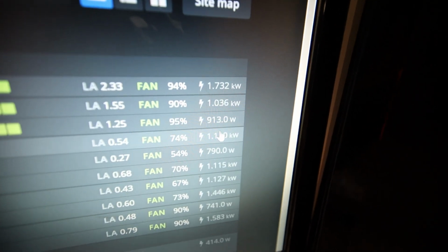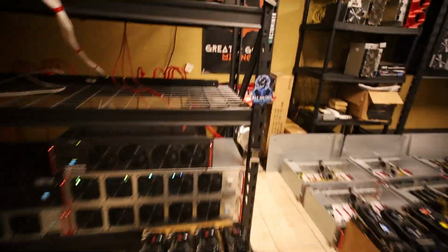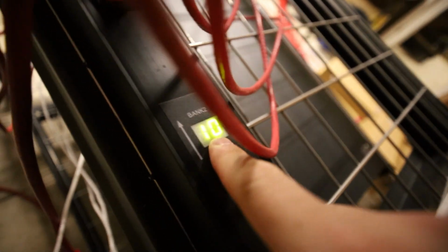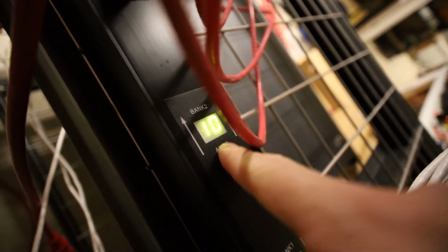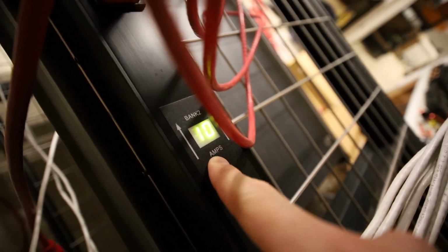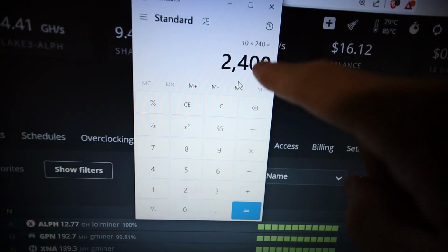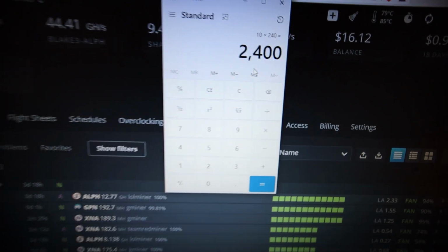So if I'm already using pretty much 2,000 watts here, and we can verify this on the PDU itself because there is a meter on it, right? So we are at 10 amps. What's 10 amps times 240? That means I'm probably using almost 2,400 watts.